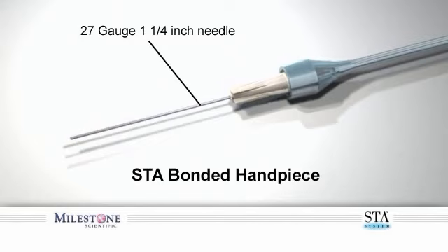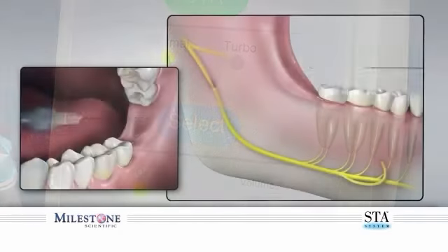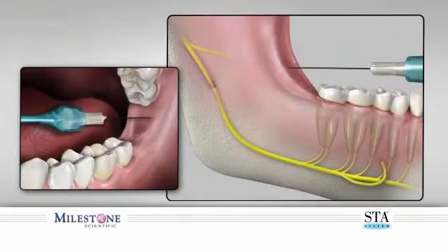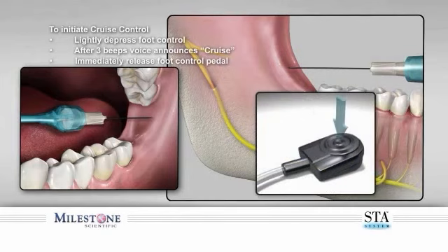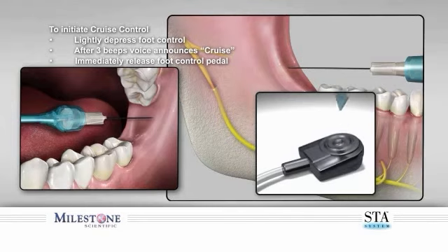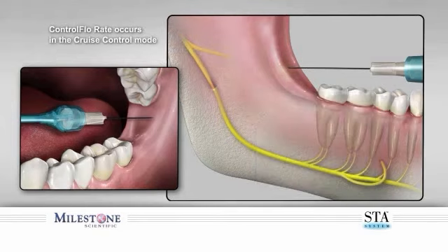Set the wand to the normal mode. Approach the site as you would normally using the traditional anatomical landmarks of the oral cavity. To initiate the injection using cruise control, slightly depress the foot control. After three beeps, you will hear the wand system announce 'Cruise.' Immediately release the foot control pedal to enter into the cruise control mode. This allows the controlled flow rate to continue to dispense anesthetic solution, creating an anesthetic zone in front of the tip of the needle.